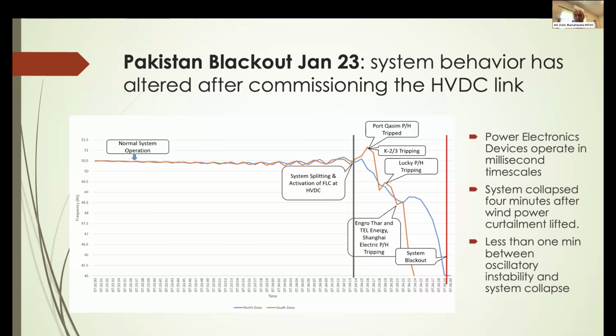This blackout was unique and extremely worrisome because it actually happened after we lifted wind power curtailment. And you see here the black line. So we lifted curtailment at 7:30 in the morning, and we noticed an oscillation at around 7:33. This is a low frequency oscillation that is typically between 0.2 and 2 hertz. It just superimposes on the main 50 hertz frequency. But as this oscillation increases, you start seeing it in the main 50 hertz frequency. So that's what you see here as the two lines start deviating from each other.